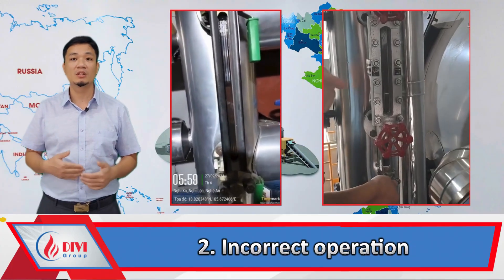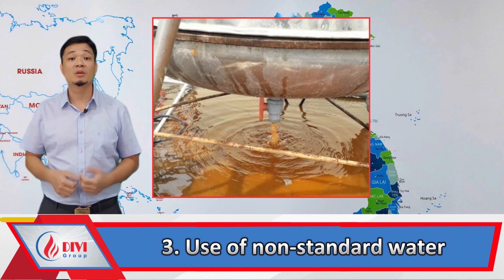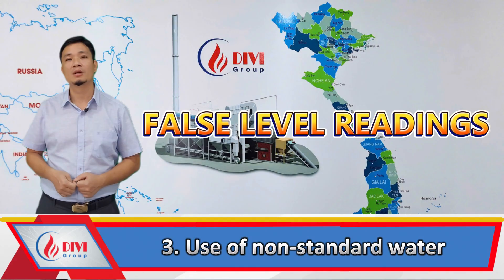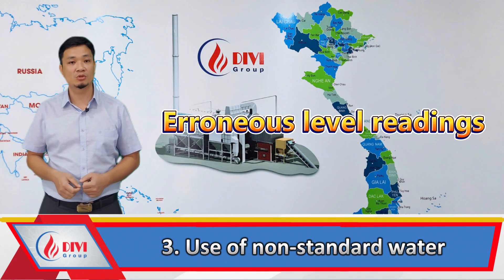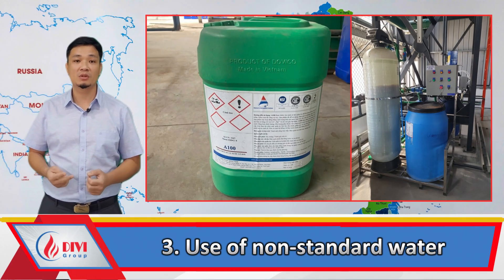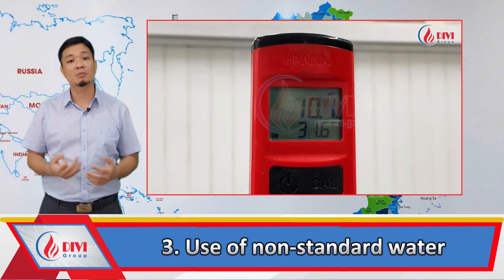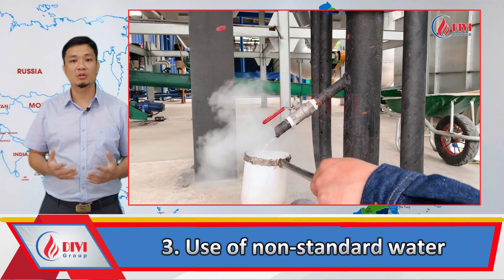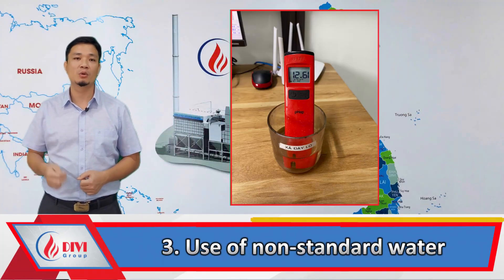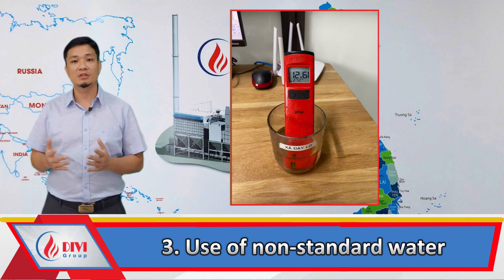Cause 1.3: use of non-standard water. Water containing impurities or untreated water can cause foaming, leading to inaccurate readings on the sight glass. This phenomenon is often referred to as false level readings or erroneous level readings in the thermal industry. This issue can occur when excessive water treatment chemicals are used, causing the pH level in the boiler to rise, resulting in foaming and inaccurate readings. This can be easily detected by observing the blowdown water — if the water appears milky white, it usually means excessive chemicals have been added, causing foaming and heavy water carryover into the steam, which negatively affects production.